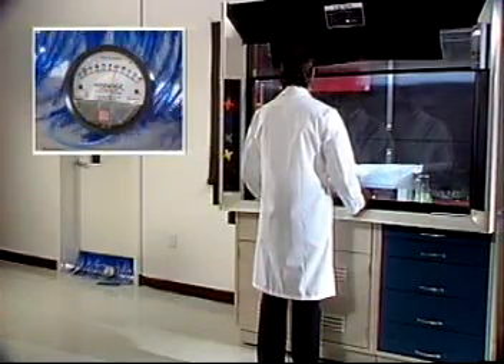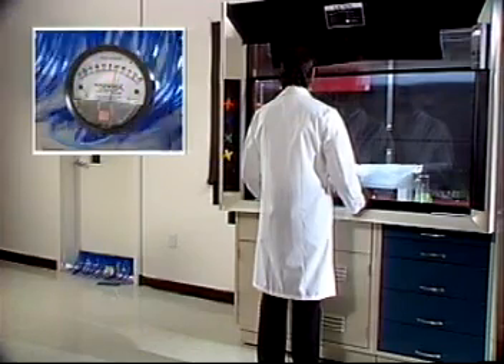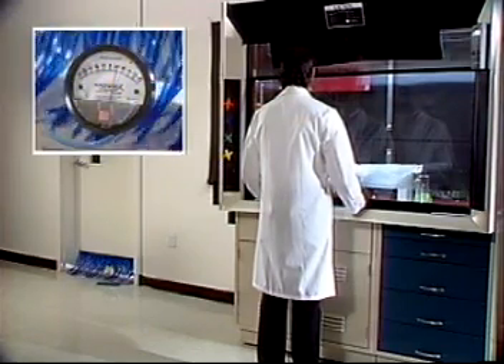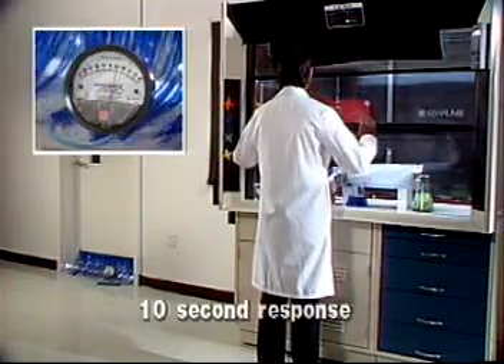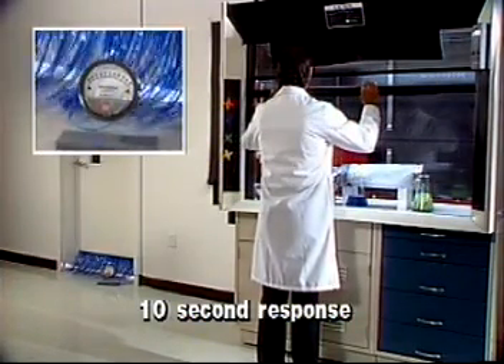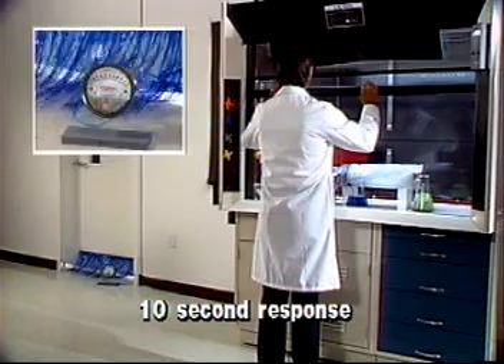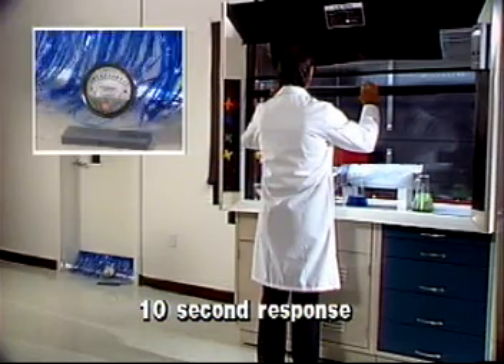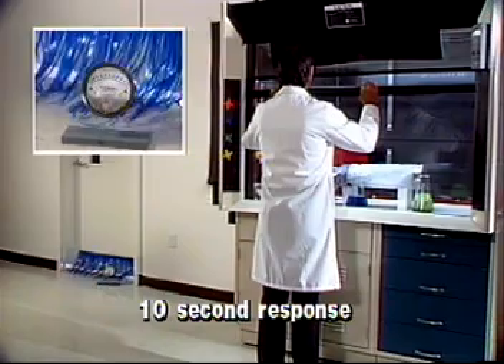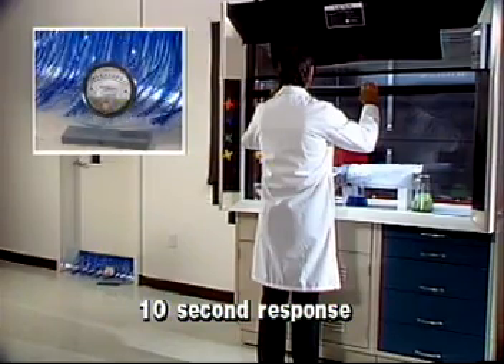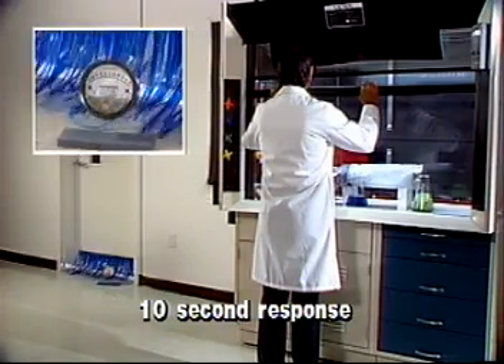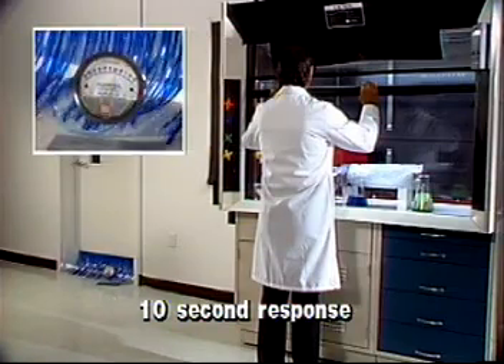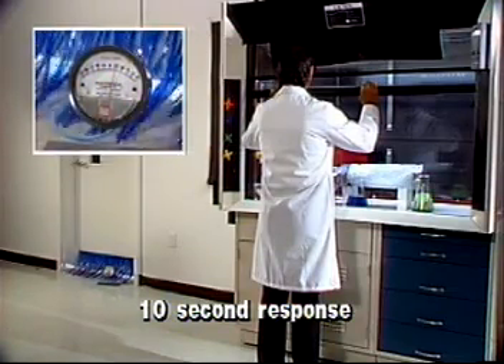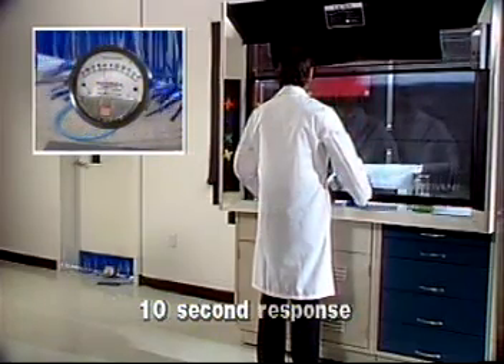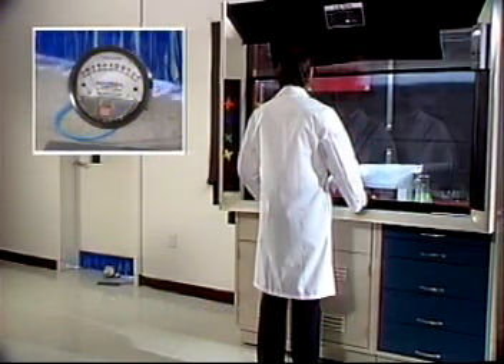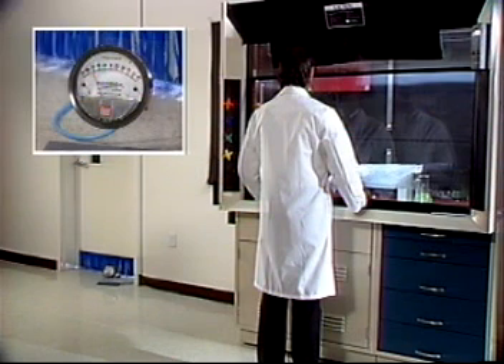Now we will filter the control signal to simulate a 10-second delay in the tracking of the room supply to the hood exhaust. Notice that when the sash is raised, the negative room pressure is again dramatically increased. When the operator lowers the sash, the room pressure again clearly changes to a potentially unsafe positive state.